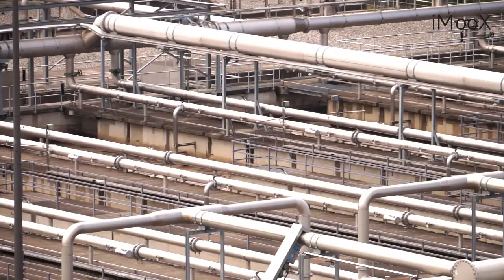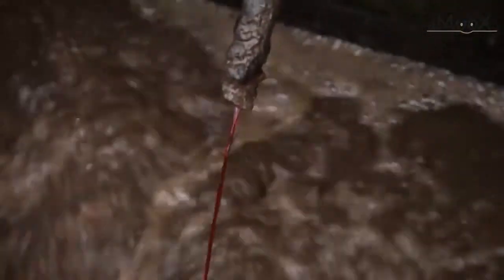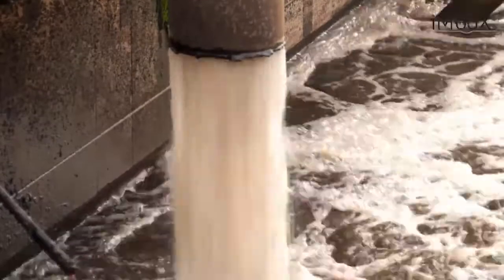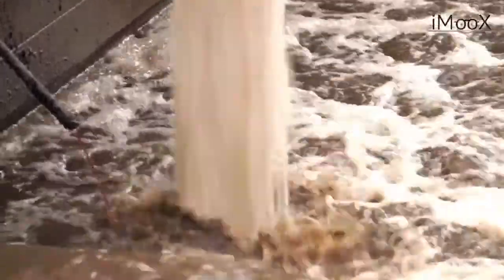During the biological degradation, flocculating agents are added in order to facilitate the separation of water and sludge. For example, iron dissolved in hydrochloric acid binds the phosphorus content by building heavy complexes that sink faster to the bottom.